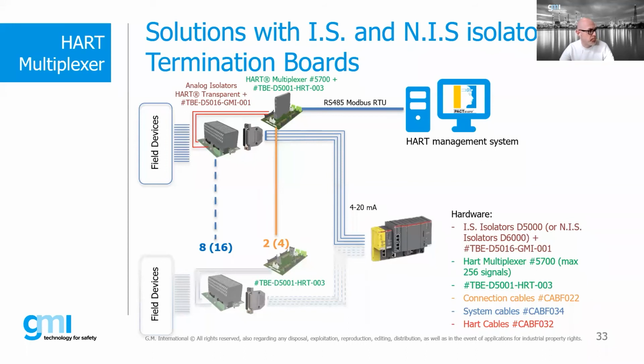In the slide, we will see an example when we use the termination board with on board a single channel device. Yeah, in this case, you have 8 boards for the modules and 2 boards for the HART communication, or 16 boards and 4 boards. So the brackets are different, and so it's completely different. We can use here also isolators, as Massimo said, single or dual channel. So in this case, the example is for single channel, but you can also improve your overall cost by using dual channel isolators. Then you have different numbers to be considered, but of course, you can decide project by project.